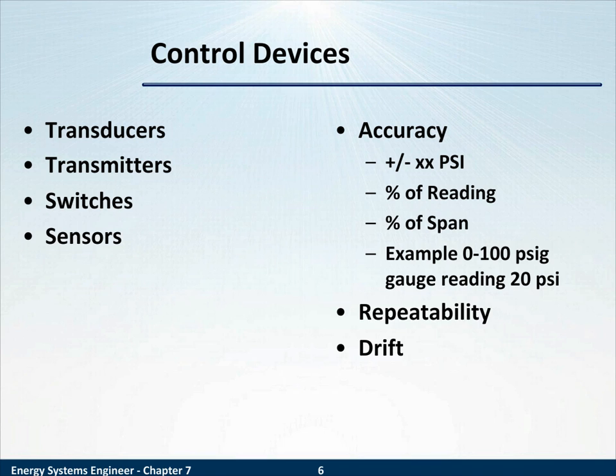A transmitter is a transducer plus a signal conditioner. An example would be converting a signal to 4 to 20 milliamps so that it can be seen as an input by a control system. A switch is a two-position device: on, off, open, closed. Sensors are input devices, devices that measure some variable of interest.